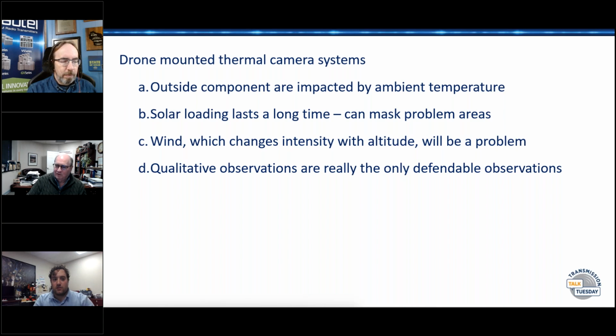Solar loading is something that will make you miss a fault on a line. So do it at night, or first thing in the morning, because it'll mask issues. Light is such an important factor - it's not just the heat from the light. If the sun is setting and there's still light touching the tower, it'll show up as radiation on your camera. You want to get rid of all the variables that you can, so you can get down to the real data.